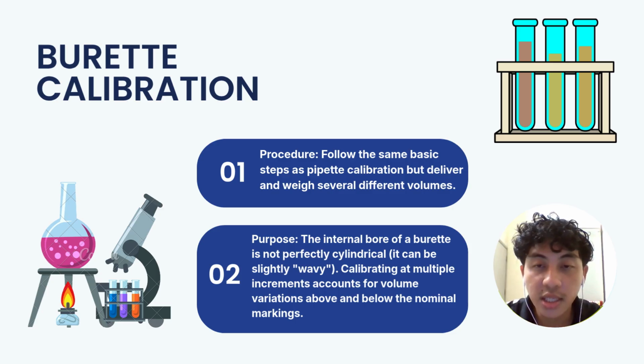So next is the calibration of a burette. As for the procedure, it is the same basic step as pipette calibration, but deliver and weigh several different volumes. So what is the purpose? The internal bore of a burette is not perfectly cylindrical and it can be slightly wavy. So calibrating at multiple increments to account for volume variation above and below the nominal markings is needed.